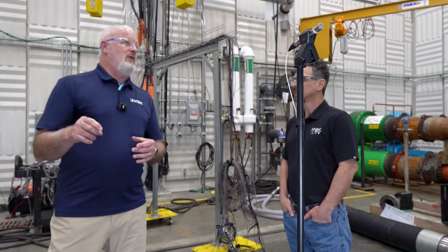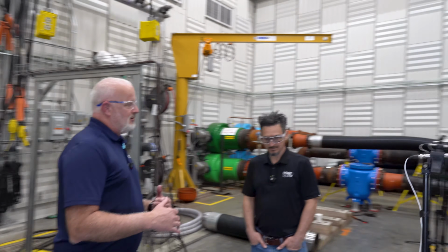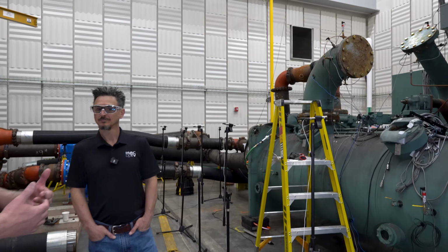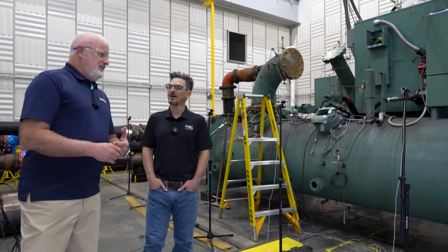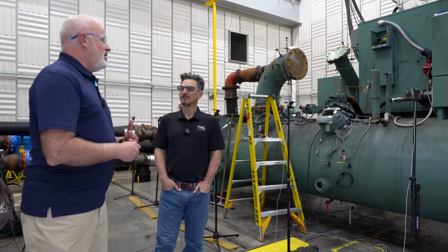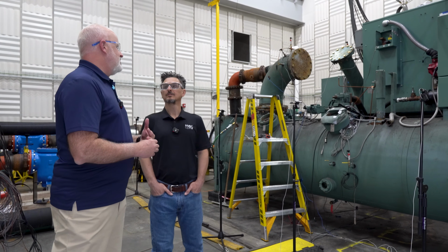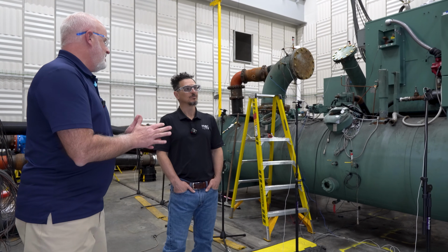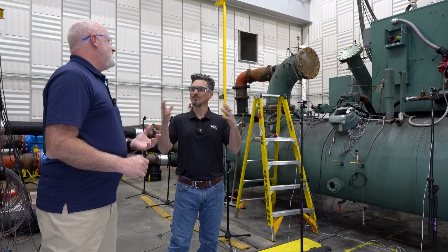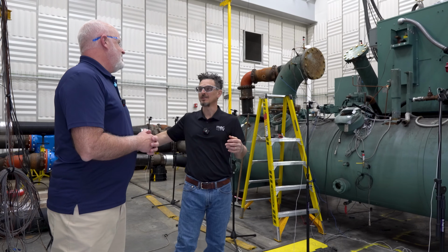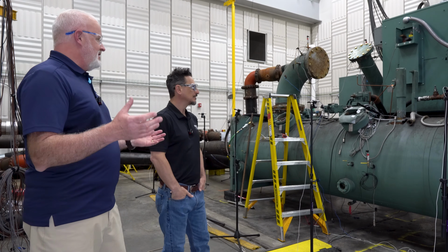This is the only room we have that will test sound of a water-cooled chiller. All of the other ones are for air-cooled chillers. Got it. And are we calculating sound power or pressure here? Actually here, we are measuring the sound power. Total sound. So sound power versus pressure: if you think of a heater, the power is the total heat it puts off. Correct. The pressure is whatever heat you feel where you're at in the particular room. So same thing with sound, right? It's relative, right? At that point.